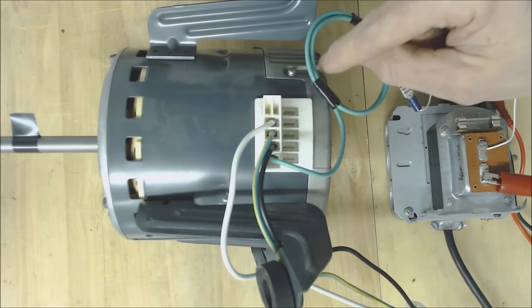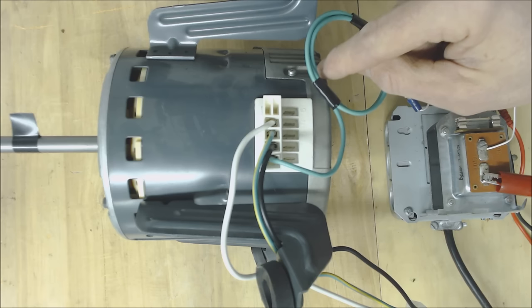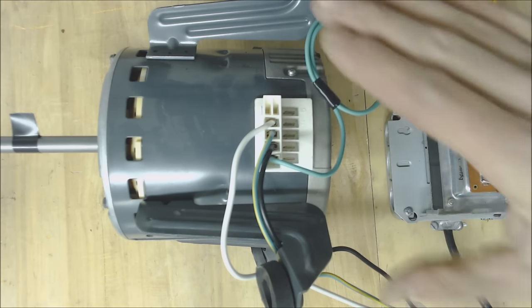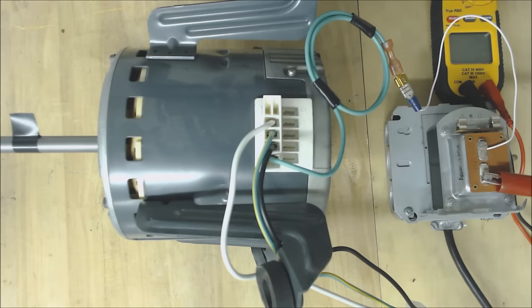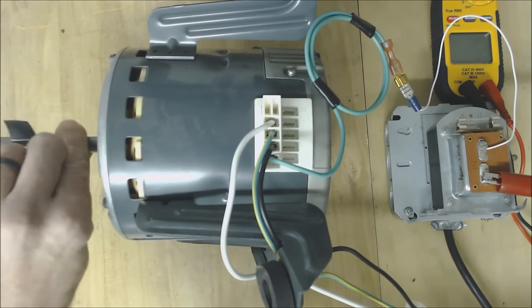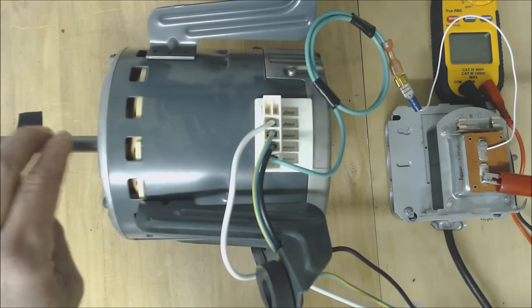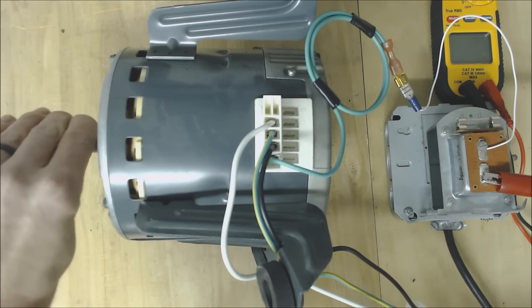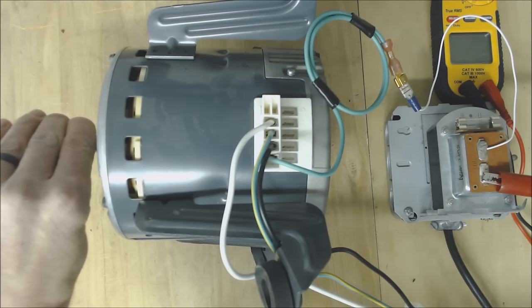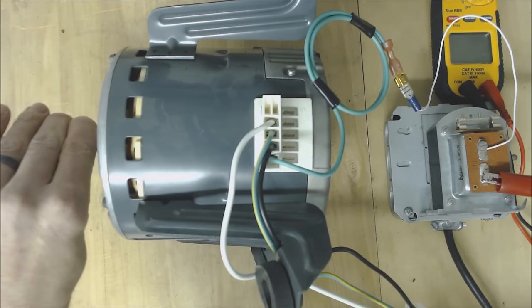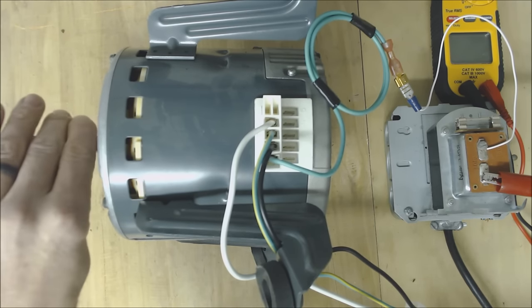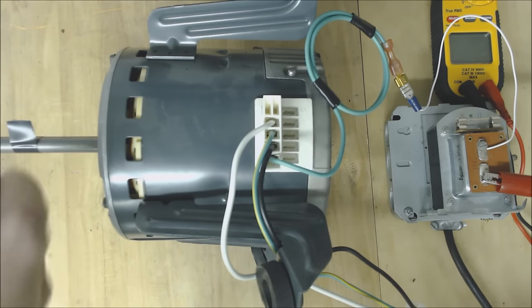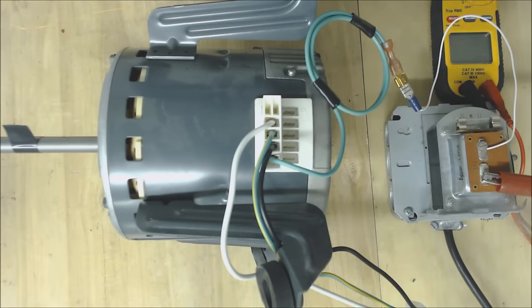So we're going to take this cover off of the module and we're going to test the motor. Also before you even bother doing any of these tests you should always check your blower motor wheel. So you make sure that you have the power off to the furnace or the air handler and you put your hand in the blower wheel area and you make sure that it can actually spin freely that the bearings are not stuck and also that the bearings are not falling apart and there's no rocking in there. So now go ahead and take this apart.